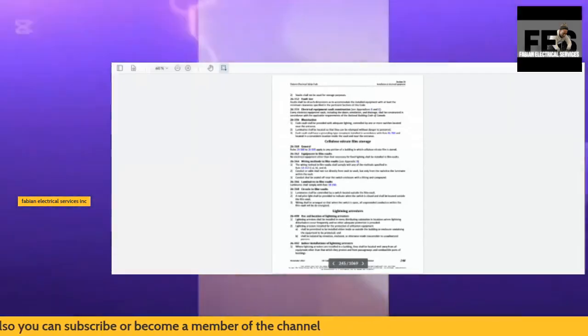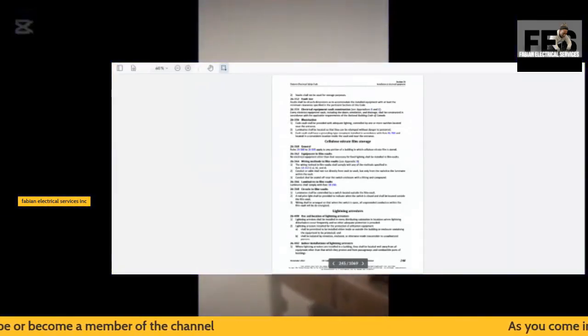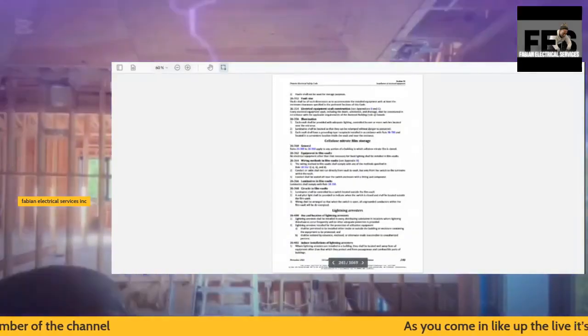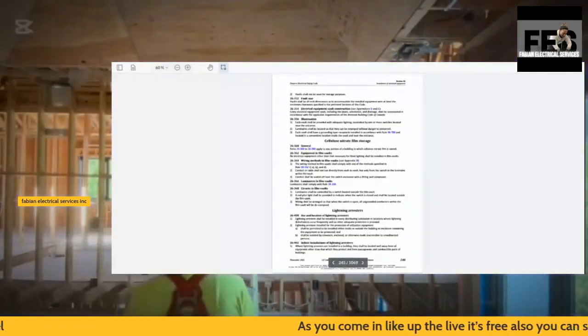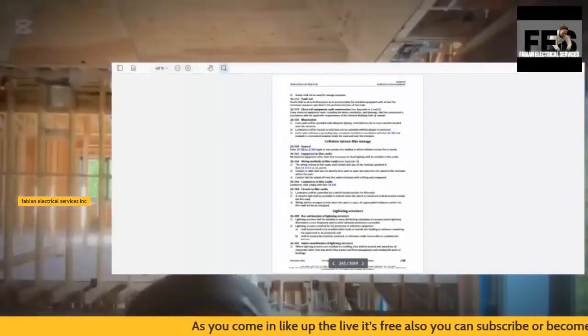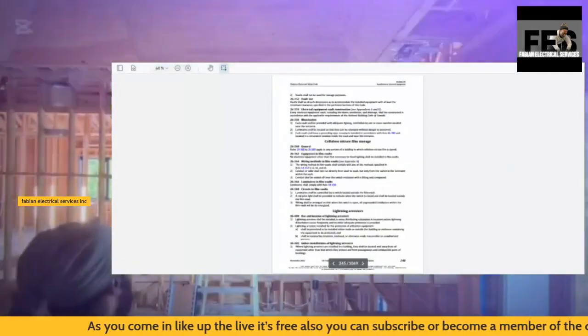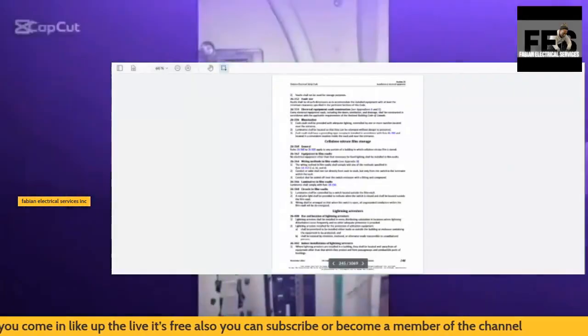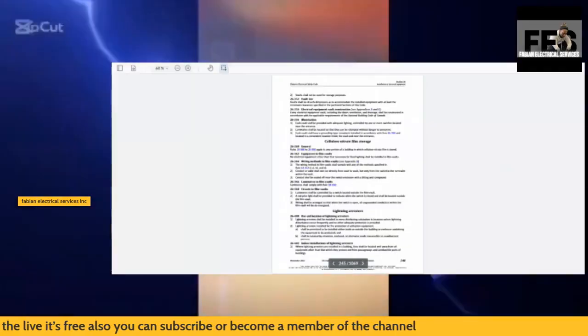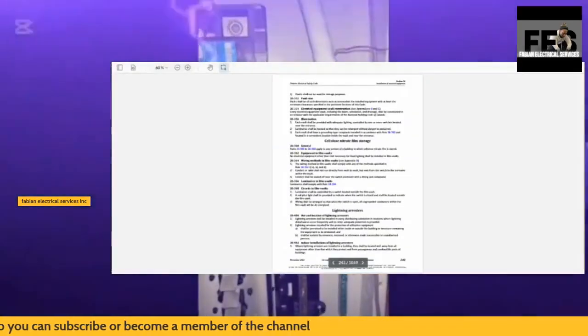Working space, you're supposed to have a clear working space of at least 1 meter, 3.3 feet in front of the panel is required with no obstruction. So what this means is you're not supposed to have any obstructions.